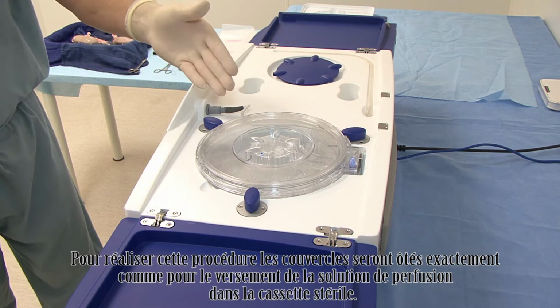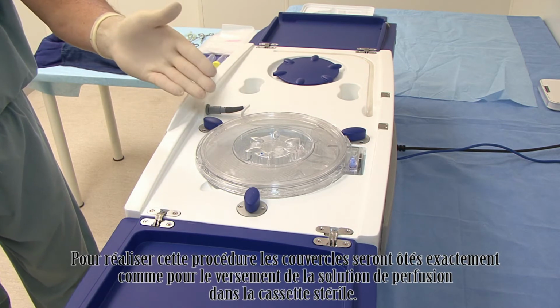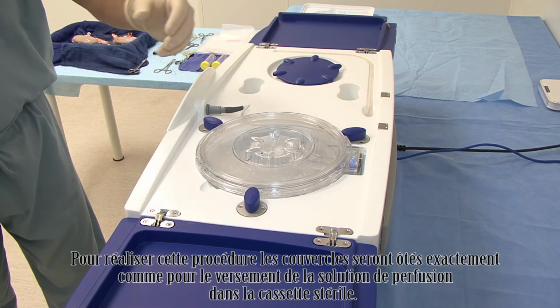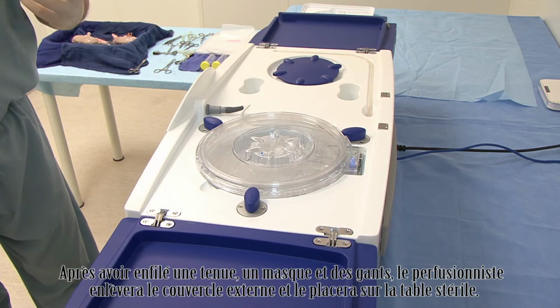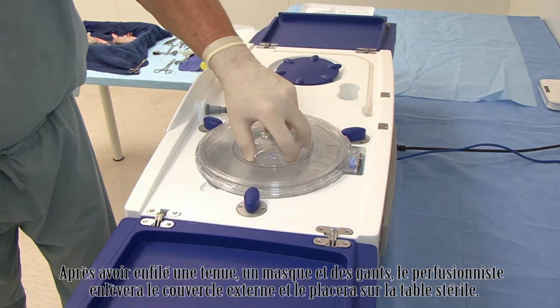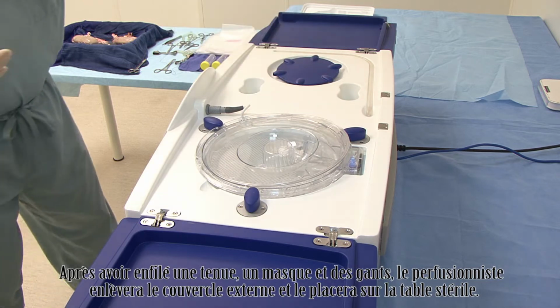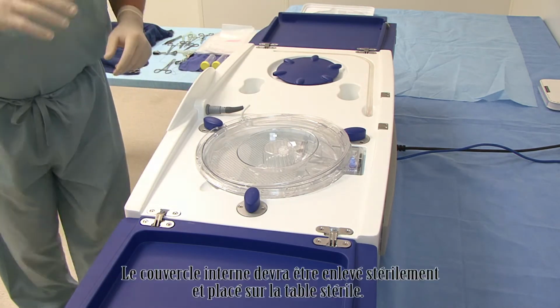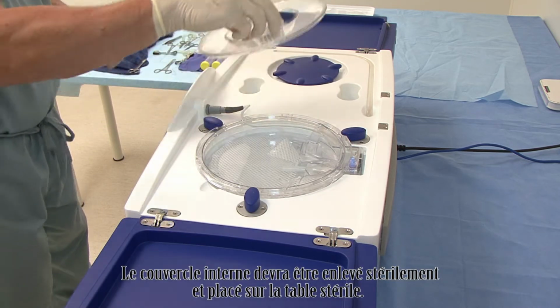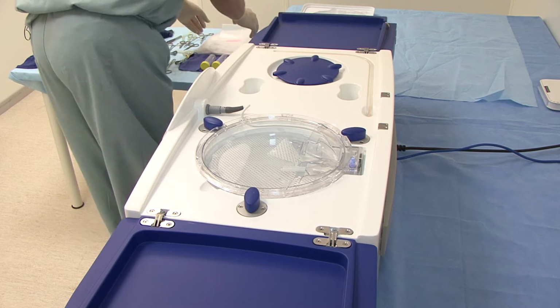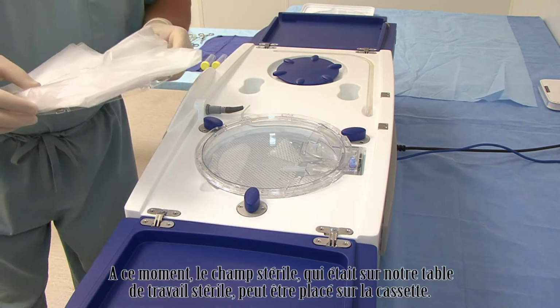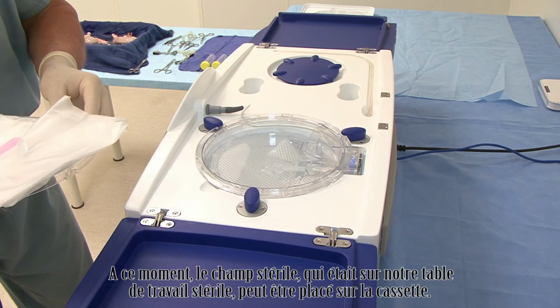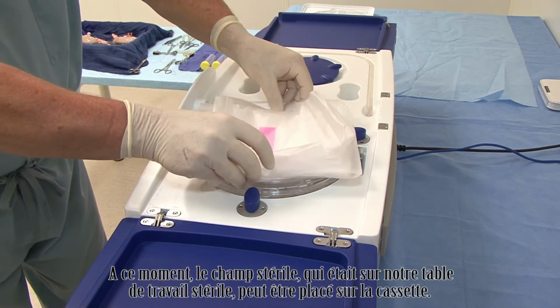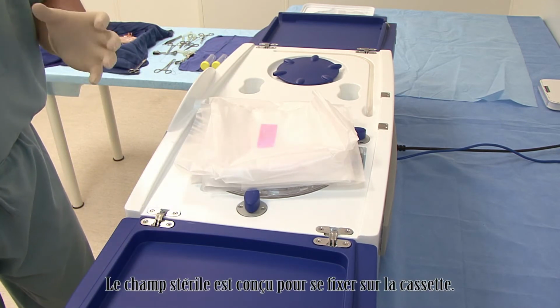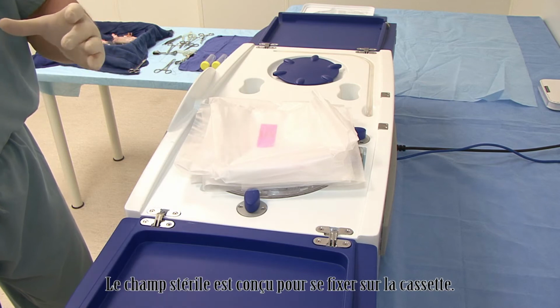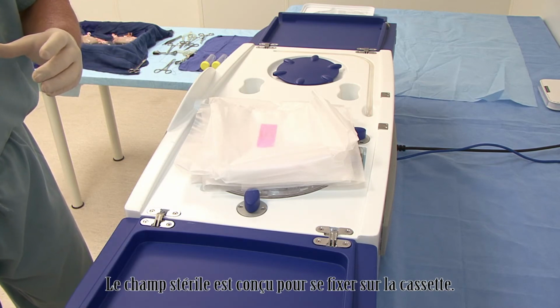To perform this process, the lids will be removed just as when the machine perfusate was decanted into the sterile canister. After donning a gown, mask, and gloves, the perfusionist will remove the outer lid and place it on the sterile table. The inner lid should be removed sterilely and placed on the sterile table. At this point, the sterile drape, which has been on our sterile back table, can be placed in the cassette. The sterile drape is designed to fit inside the grooves on the cassette.